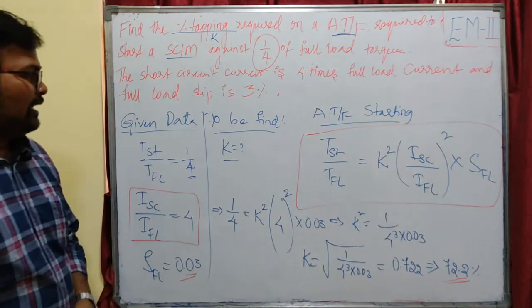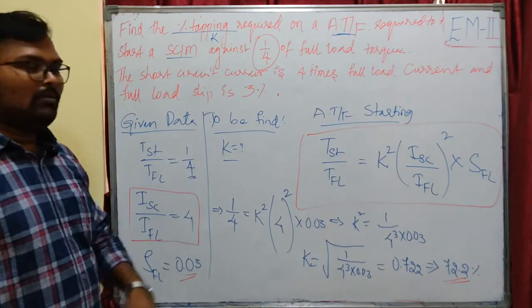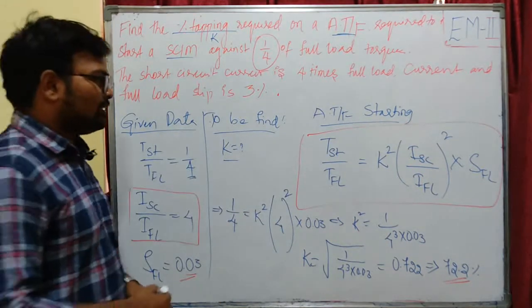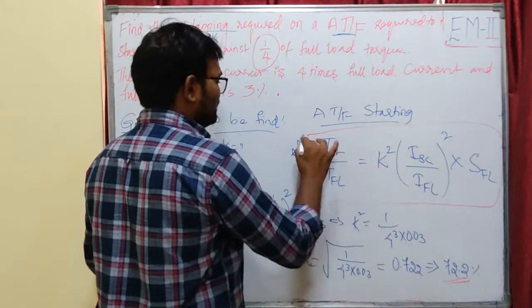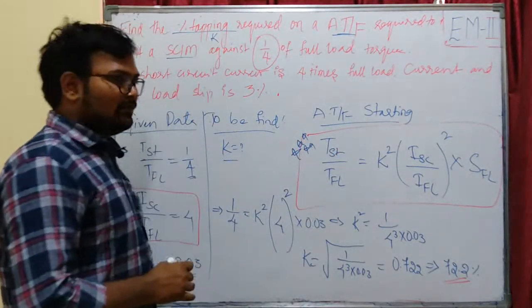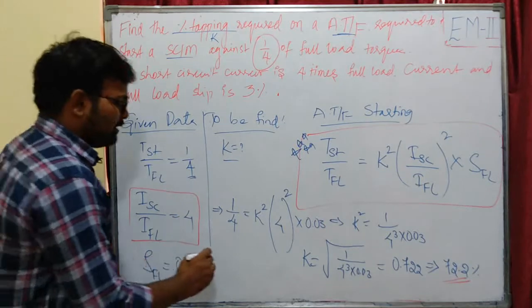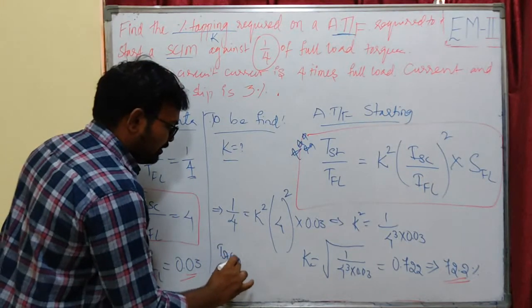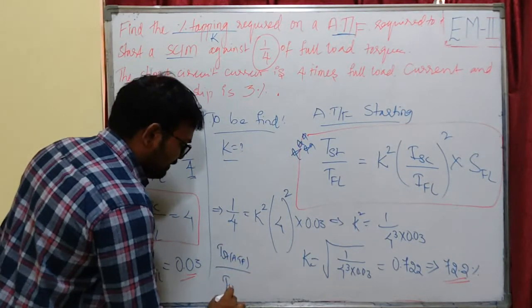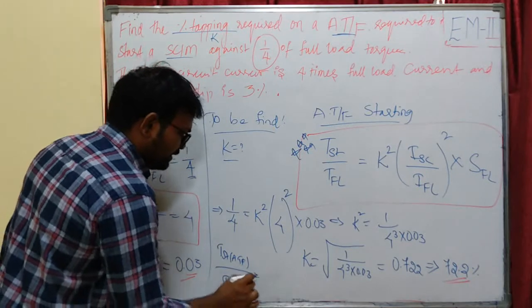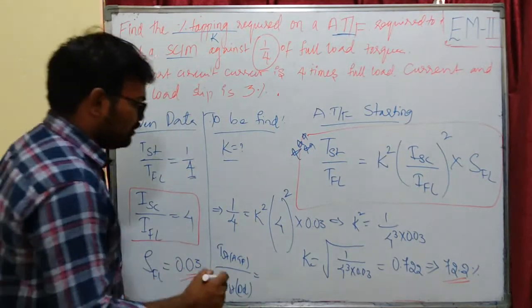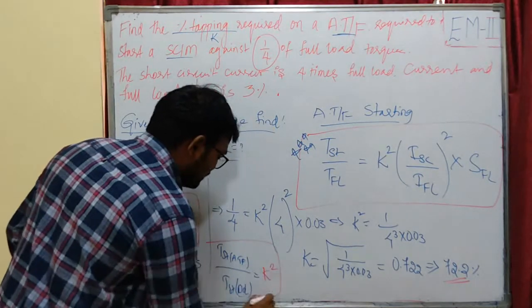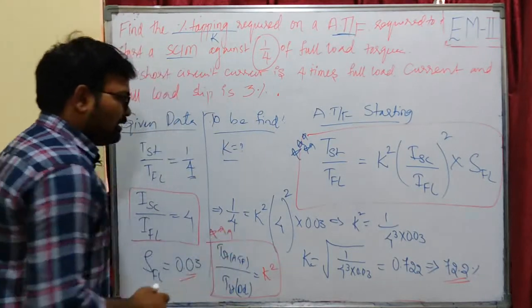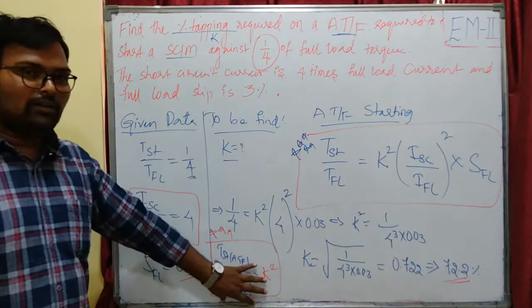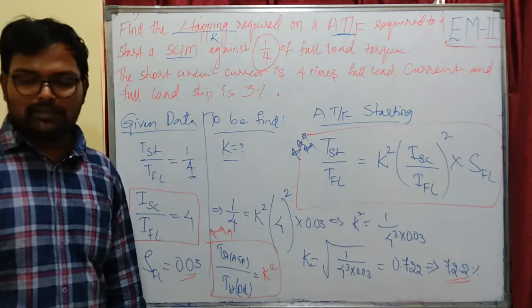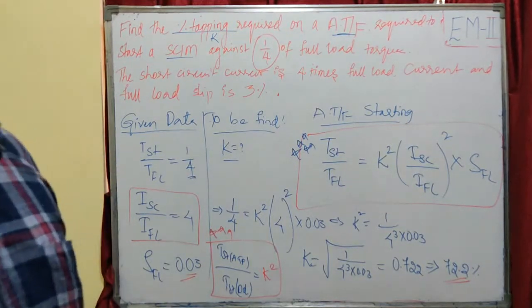I think you have a basic idea about starting torque and full load torque, and this is a very important relation. The relation for TST auto transformer by TST DOL is also very important, which is equal to percentage tapping whole square, that means K square. So these two are the important relations to be noted down. This is about auto transformer starting. In the next class we will be dealing with star delta starting. Thank you.